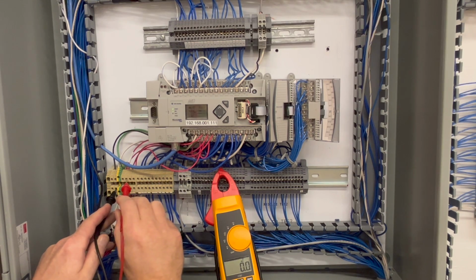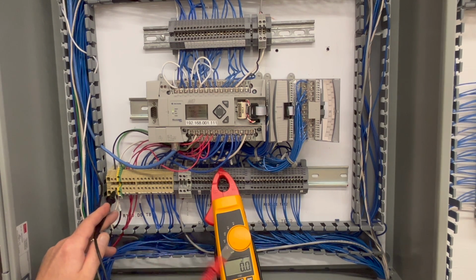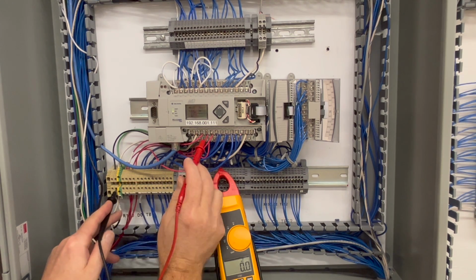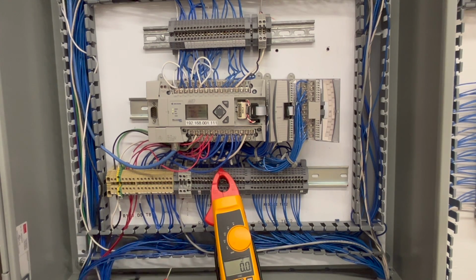I can even trace that down to here, 120, 120, and I know if I trace that back to the green light that's on over there, that we would have 120 volts flowing through there. All right, so now we know that contact's bad and we can feel confident that we may have to replace this PLC when we report back to our bosses. All right, so that's just a little introduction into troubleshooting a PLC output.